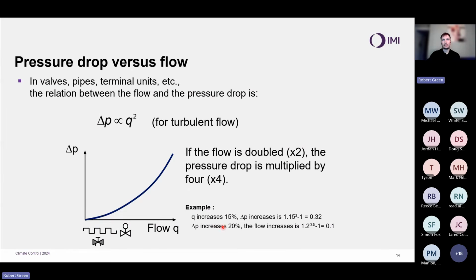So if, for example, I would like to increase my flow by 15%, you might say, well, that's only a relatively minor increase. But for that case, we would have to increase the differential pressure by 115% squared, or 32%. So to get a 15% increase in flow, we require a 32% increase in differential pressure. Now, bearing in mind, what is the only component that increases differential pressure in a system? Valves can't do it, pipes can't do it. It is only the pump that is creating a difference in static pressure, i.e. we'd have to increase my pump head by 32% to get my flow up 15%, which could be due to poor balancing that we have to do that increase.